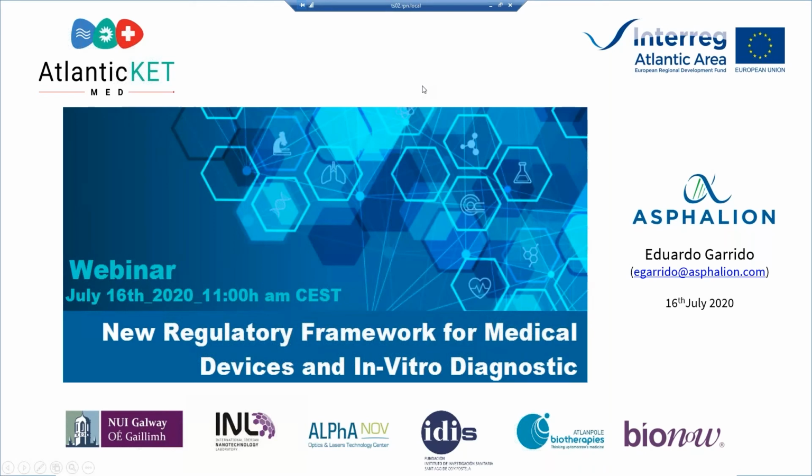What implications does branding have on CE marking? Well, branding is quite a different topic. CE marking goes prior to branding. So it doesn't have an impact on what you have to provide to obtain this CE marking. I mean, the only thing you have to have clear is the indications and intended use you're giving to your device, but that's something you've got to do before you start with the branding of your device.